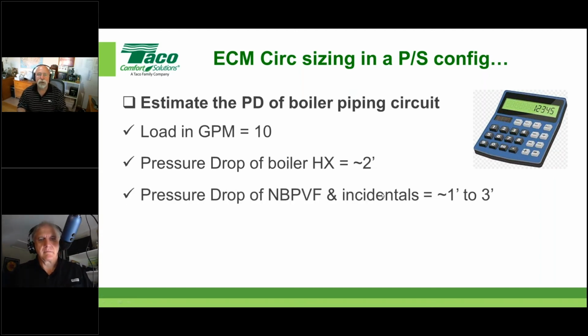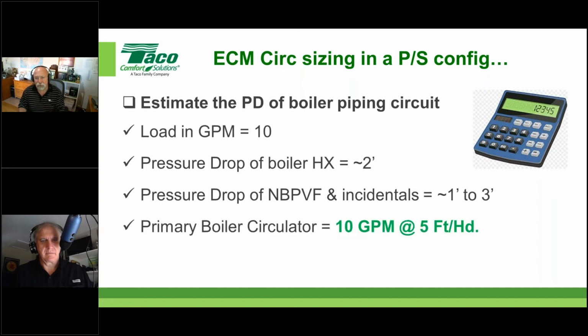If I throw some numbers in there for the incidental pipe, valves and fittings that hook up to the boiler, again, this is where we were talking about double dipping. Don't double dip here, okay? I'm going to go ahead and just put 2 foot and conservatively 3 foot. So I need a pump that'll do 10 gallons a minute at 5 foot of head.